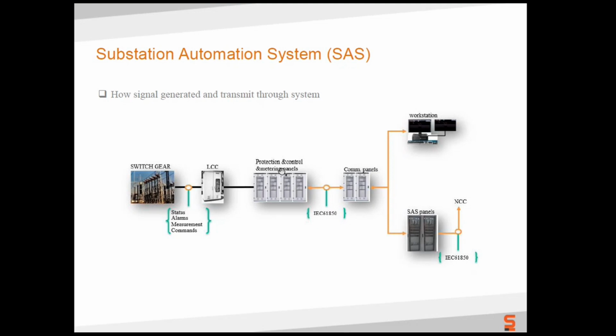So in SAS based systems, protection, control, and metering is limited to a very limited number of panels. What is there inside these panels are intelligent electronic devices, IEDs. They are electronic cards, electronic relays designed by manufacturers like Hitachi, ABB, Siemens, GE, based on specific IEC based protocols.